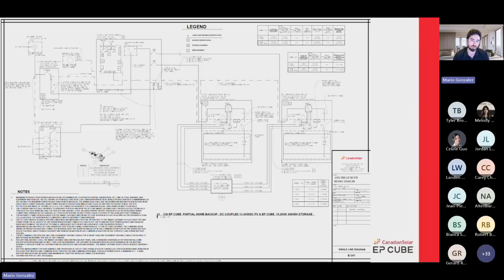This is a whole home. As you can see, there's only one sub panel that we're feeding, connecting the gateway to the loads. Then these two 40 amp breakers go to the inverters. You need a 2-pole 40 amp breaker per inverter, and these are our extension ports, right? Each rated for 100 amps. We recommend connecting up to 80 amps, just for the 120% rule. And yeah, you can do AC coupling, generator, EV charger, and those ports. You can even do some load shedding if you want.